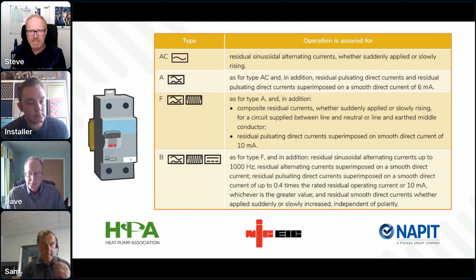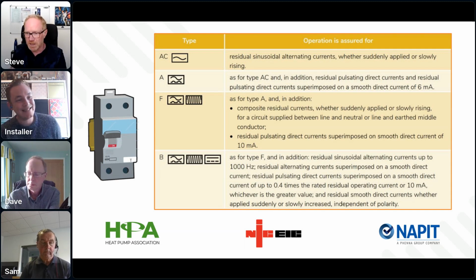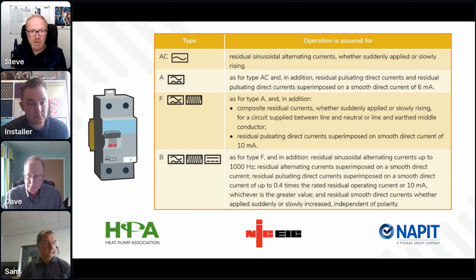As our electrical equipment gets more and more complicated, this is why type Bs and type Fs are becoming more and more common. We've already looked at type ACs, which we don't use anymore because we haven't got standard resistive loads. Because of the DC components, they're going to trip all day long as soon as look at them funny. Whereas your As, your Fs, and your Bs have that more tolerance. They commonly arise in installations with variable speed drives. UPS systems use them a lot, EV chargers are more common, and photovoltaic inverters all produce multiple residual currents simultaneously.